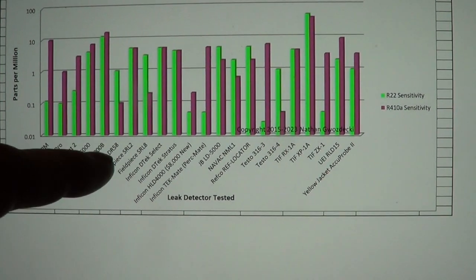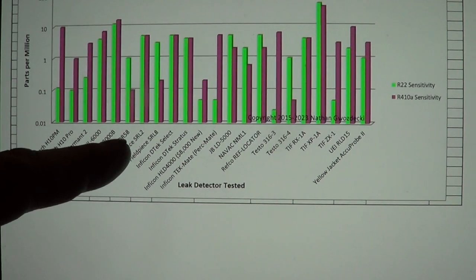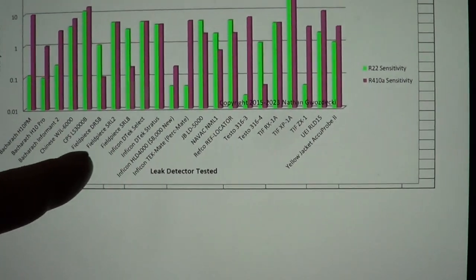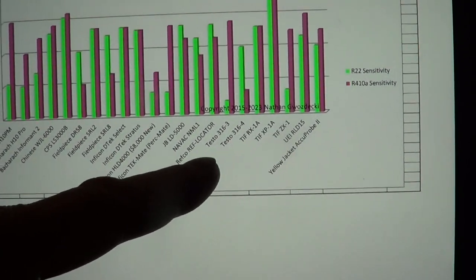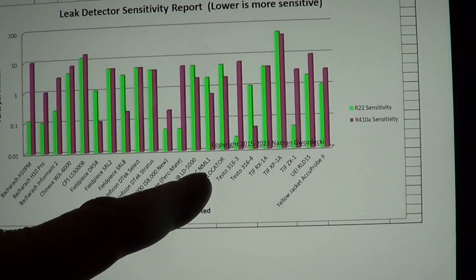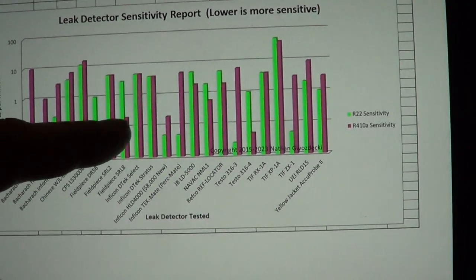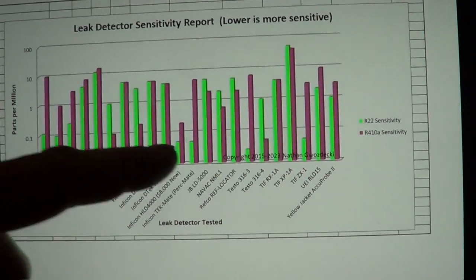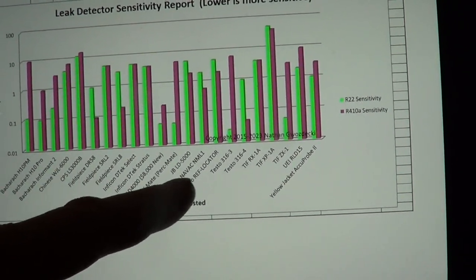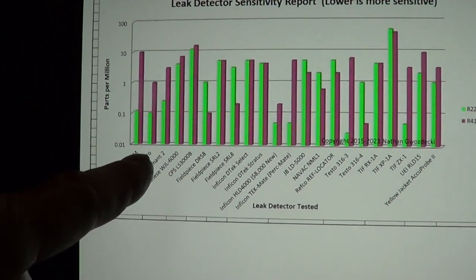The DR58 uses the exact same sensor, which is a heated diode. Actually the DR58, the SRL8, and I believe the Prowler all used that sensor, and the NAVAC is using that same sensor too. So the NAVAC was less squirrely just because they're dialing it down — they're six times less sensitive than the Field Piece. But I prefer to be more sensitive, because for 20 years I used the gold standard, which was the Bacharach H10 Pro.